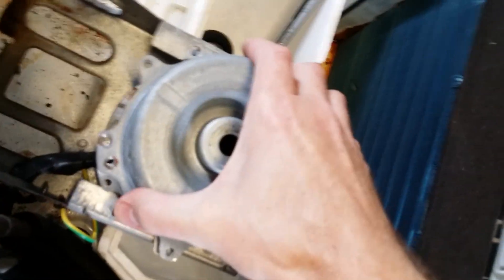Clean the shaft up — it should slide on smooth until you get down to the wider part of the shaft. I found a lot of corrosion in this thing; it's disappointing — a lot of rust. I think I'm gonna put a drain hole in here. You lose a little efficiency but this thing's gonna rust away before its time. I found some new fasteners to replace the old ones, cleaned everything up, vacuumed it out, and inserted the armature. The two halves come apart — I separated them with a chisel, very gently, tapping around the edges. Don't use force. Everything's got to be clean inside the motor — very important. I put it back together and it's spinning nice and smooth. Take pictures when you take it apart so you know how everything goes.